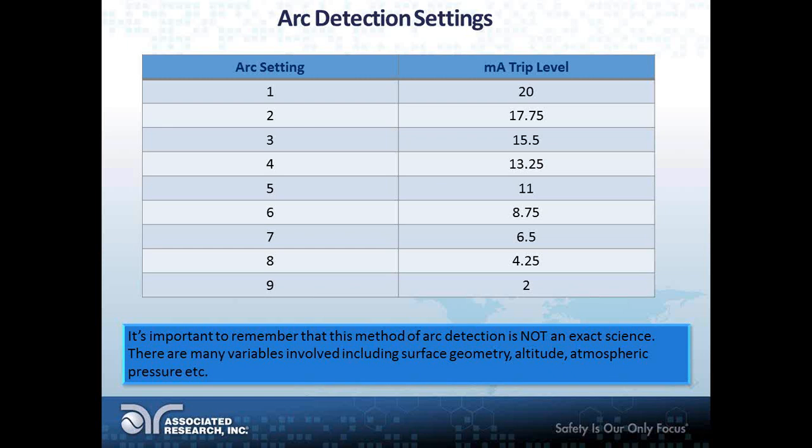Again, arc settings are seen more as a quality issue and not safety agency standard pass-fail criteria. However, you may deal with a customer who wants you to use it and considers an arc fail a true failure. That's something that is a case-by-case basis, and I can't speak on that. But there are some tough customers out there, and they require that an arc fail is actually considered a failure, and I have run into those applications as well.